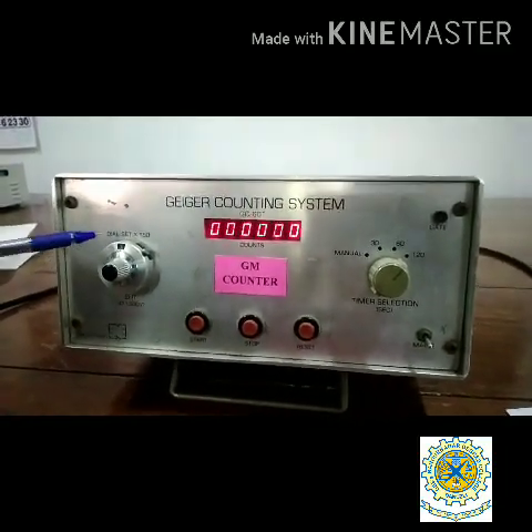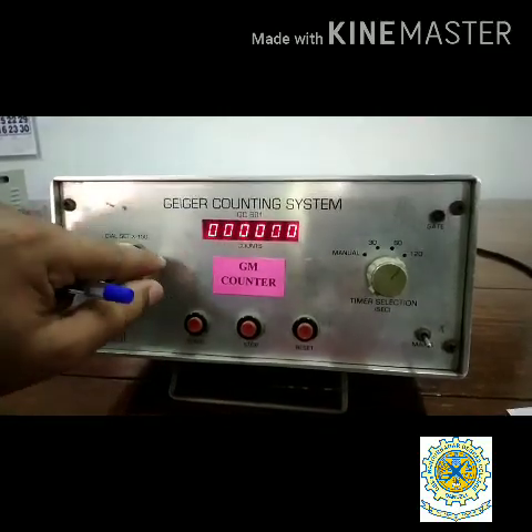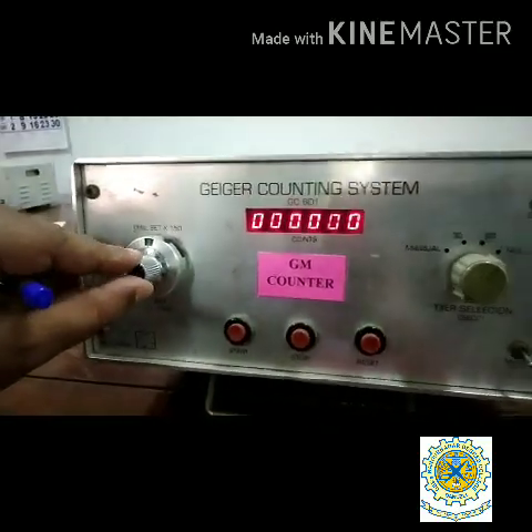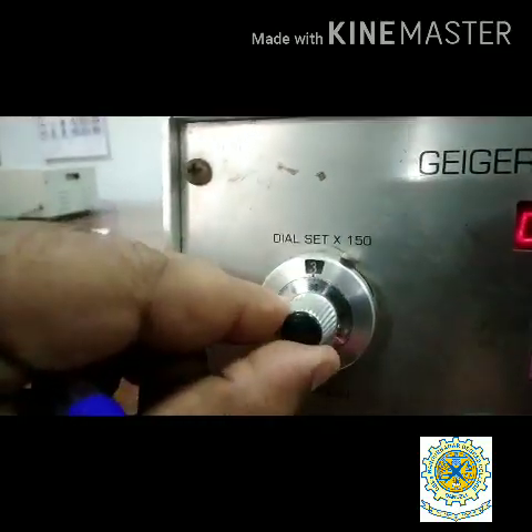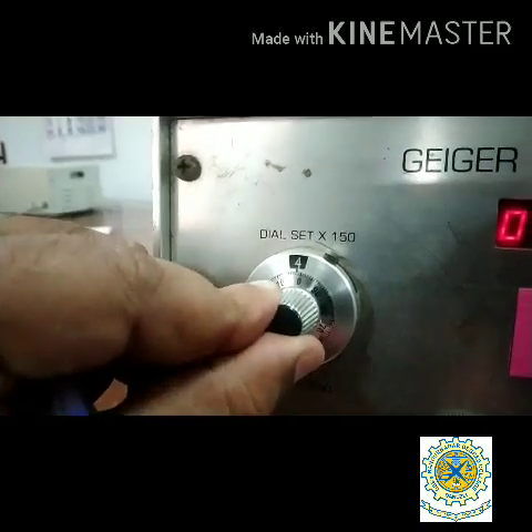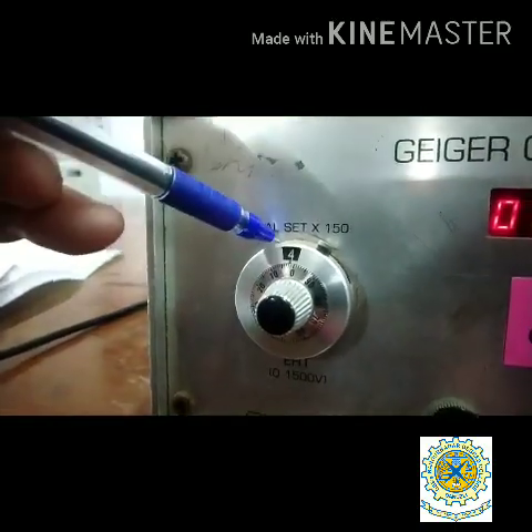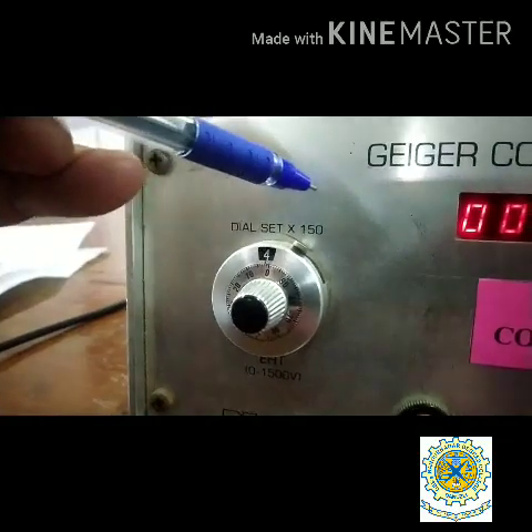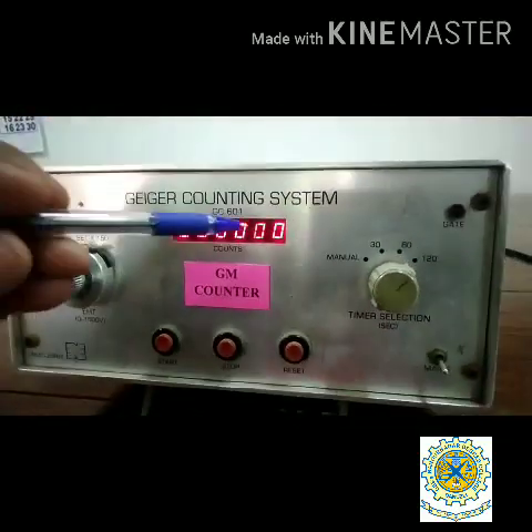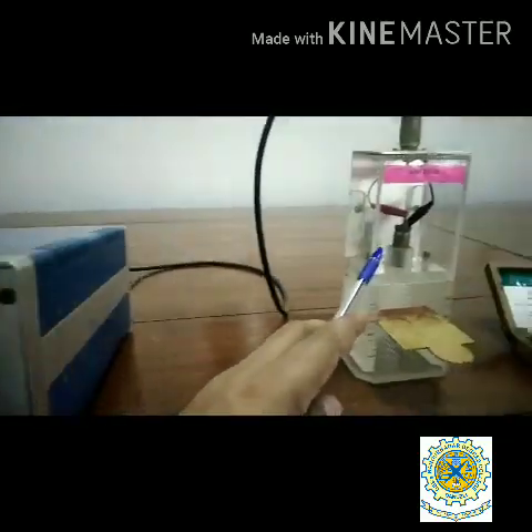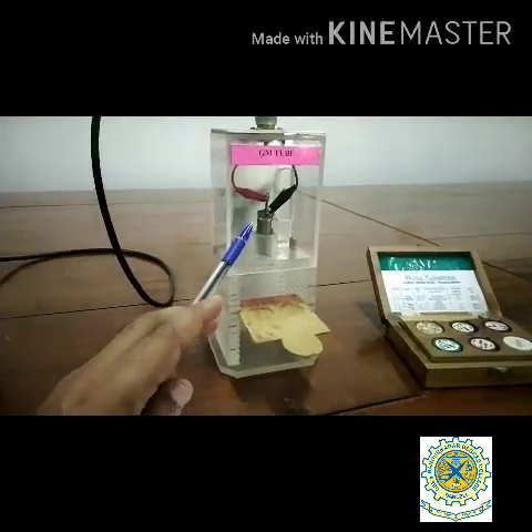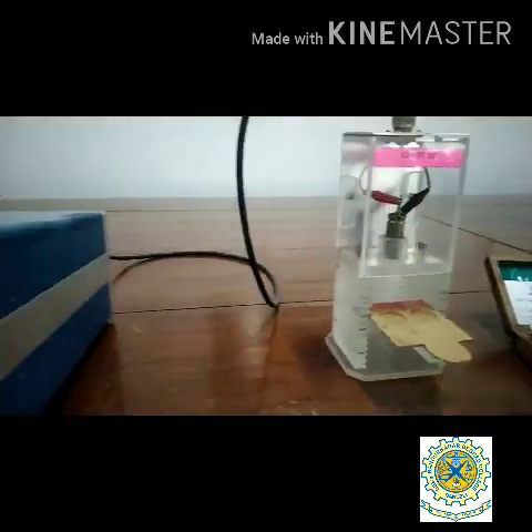This is a dial set machine, so if I change it by a certain voltage, imagine now it is at 4 multiplied by 150. That indicates the voltage which is formed here at the GM tube, that is 4 into 150, which is 600.